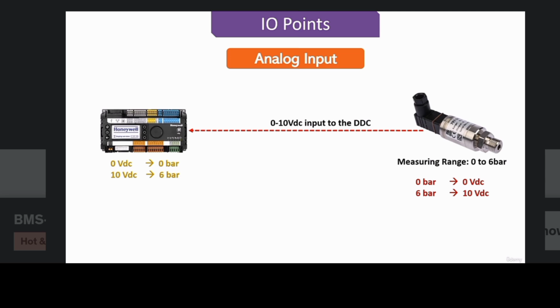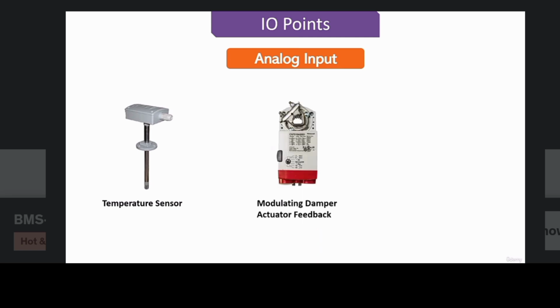So in this way, the pressure transmitter converts pressure into the electrical signal, and once it reaches the DDC, the DDC translates it back to the pressure value based on the configuration done inside the DDC controller. Other examples of analog inputs can be temperature sensors. This temperature sensor can be a thermistor, which will give a resistance value to the DDC based on the temperature. This resistance value will change as per the change in the temperature. So this is also an example of analog input because this is not fixed and it does not have only two states. Another example is modulating damper actuator feedback.